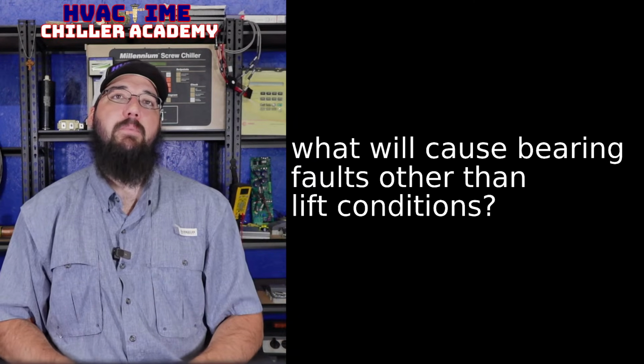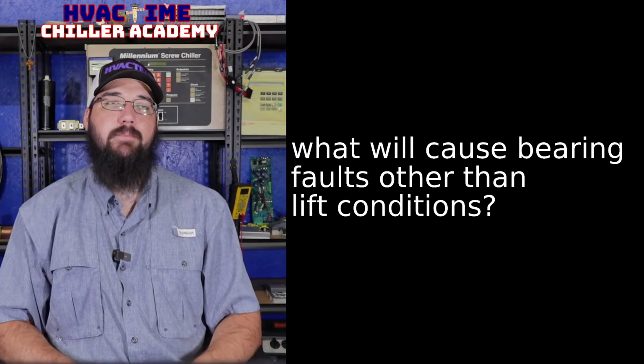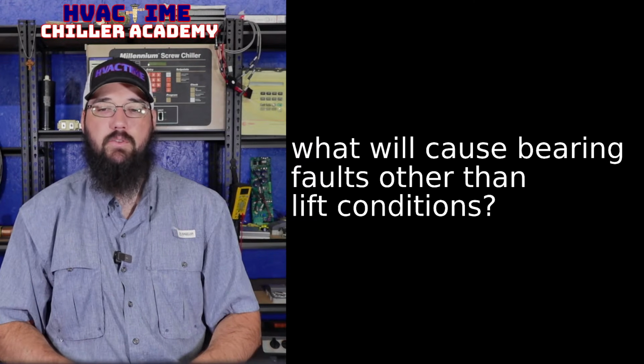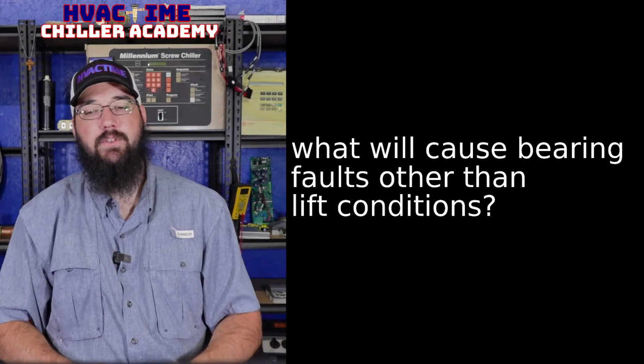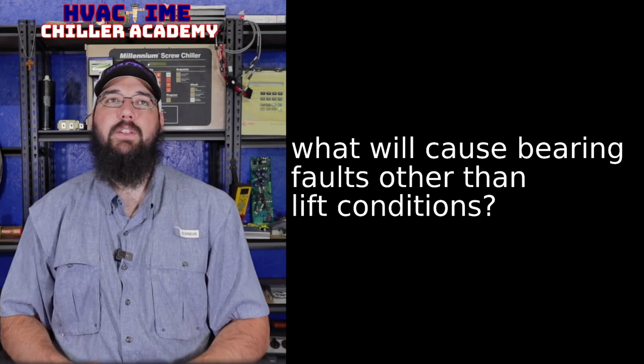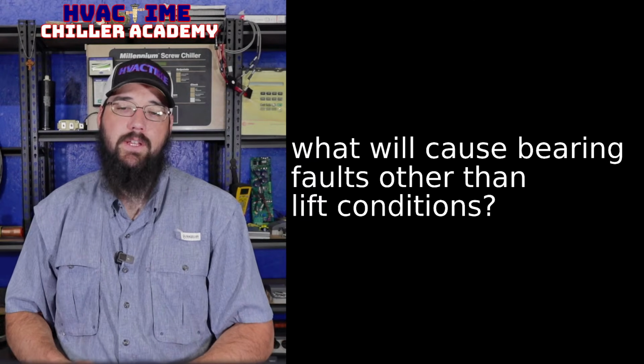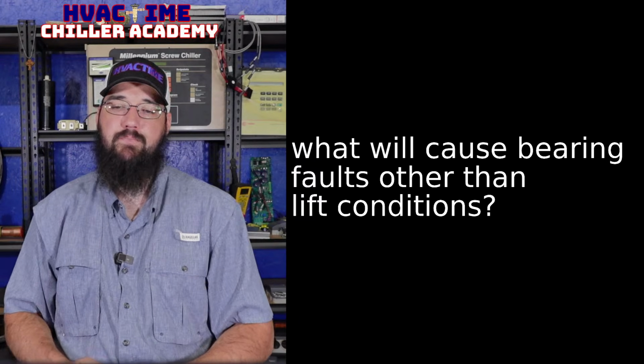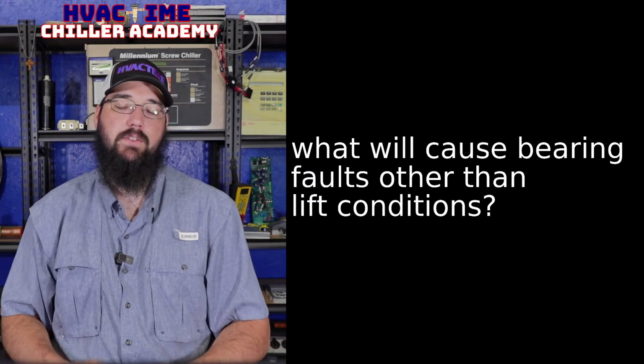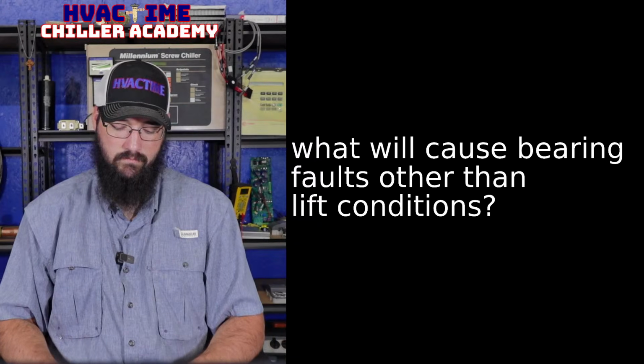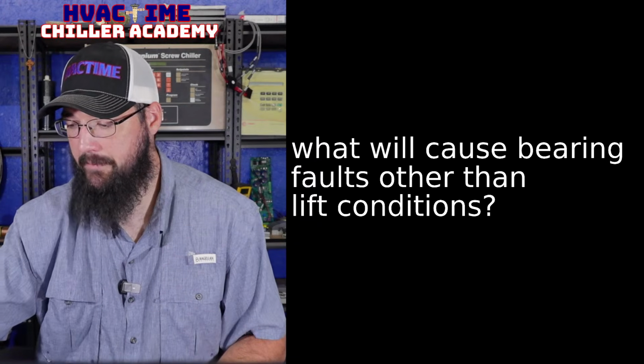Because if it's the evaporator side, you'll see it on the suction side. It will be really low superheat. And if it's the economizer side, then you're going to see it on the discharge only. You won't see it on the suction because the economizer bypasses the suction. It comes in at an intermediate point.